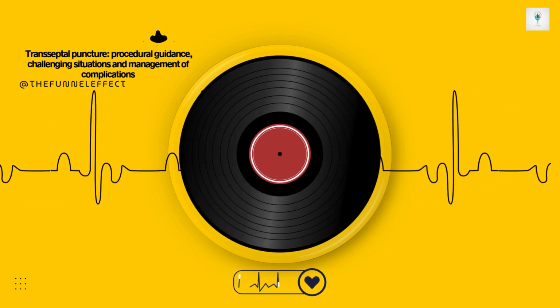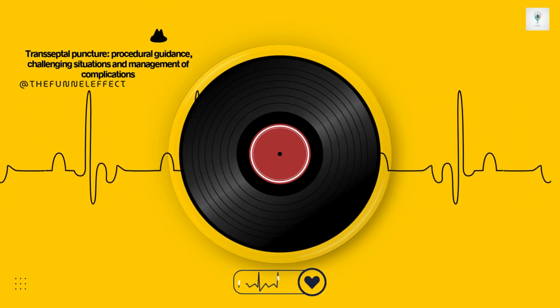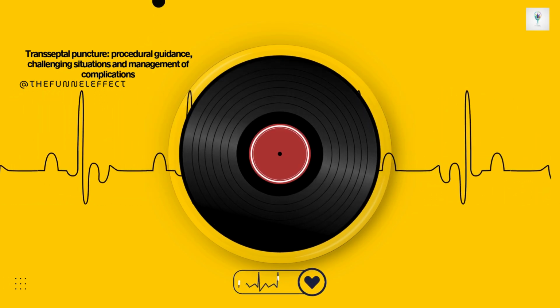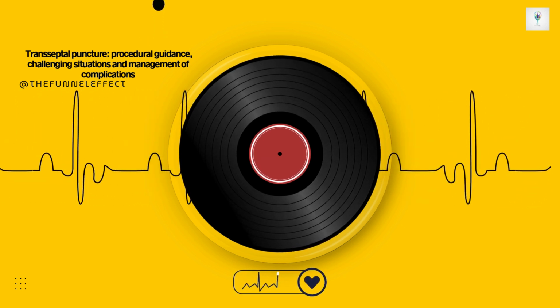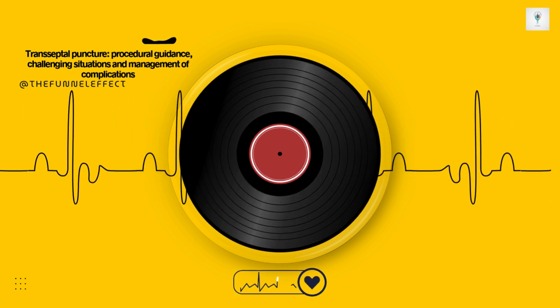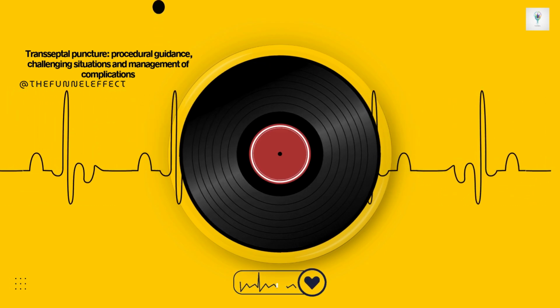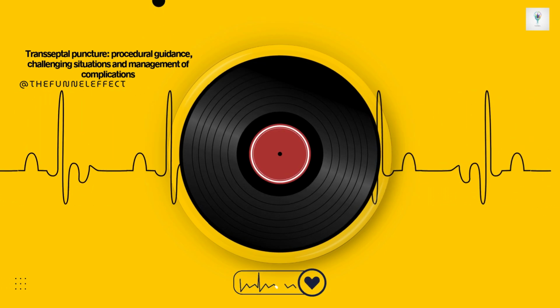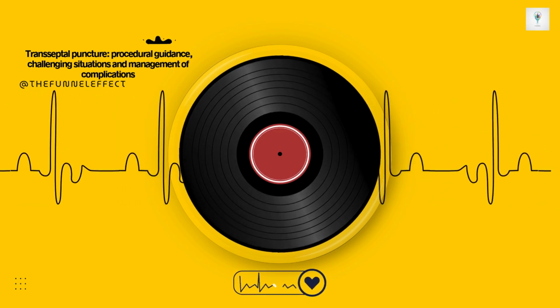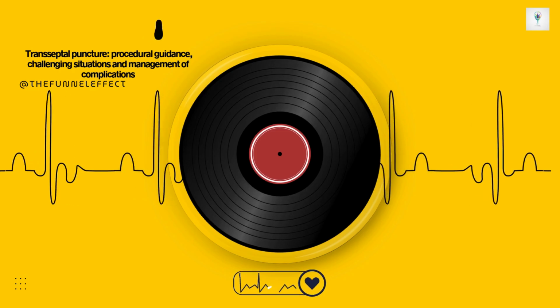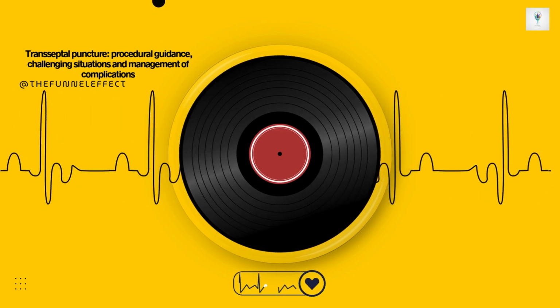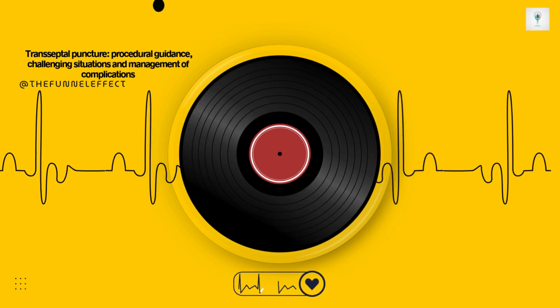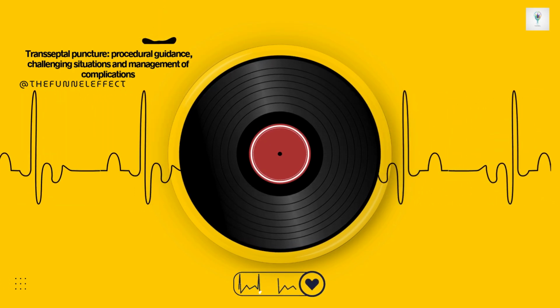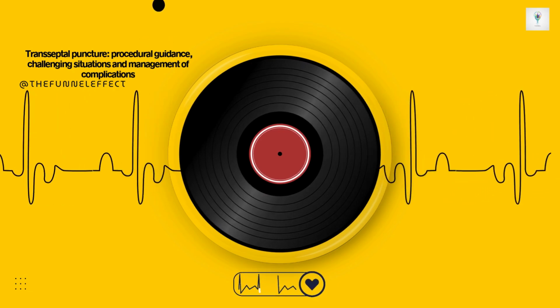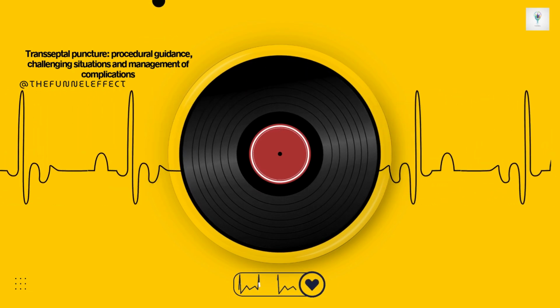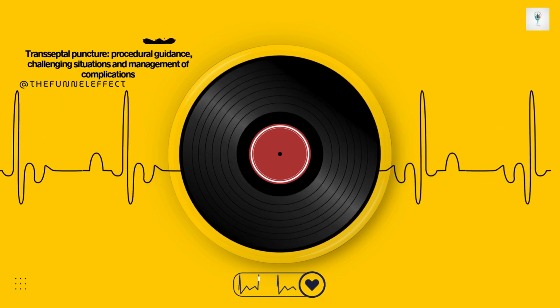And these needles aren't one-size-fits-all, are they? There are specific versions tailored to the patient's anatomy or maybe the difficulty of the access route. Exactly right. The standard BRK needle has a fairly gentle 19-degree angle at the tip. But if the anatomy is complex, perhaps a highly enlarged right atrium or a challenging SVC approach, the operator might need the BRK1. That one features a much steeper 53-degree angle. This sharper angle gives the operator more mechanical leverage to direct the tip precisely onto the fossa ovalis. It also allows the operator to hand-shape the curve of the entire needle assembly, to match the unique curvature of the patient's vasculature leading up to the right atrium.